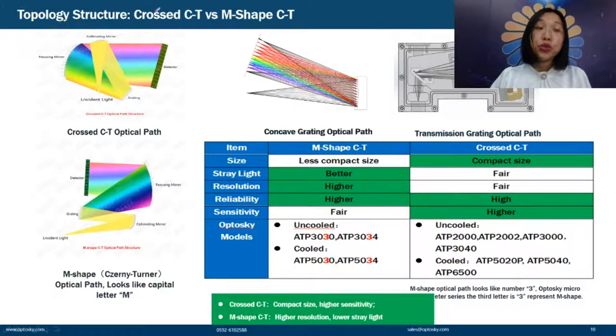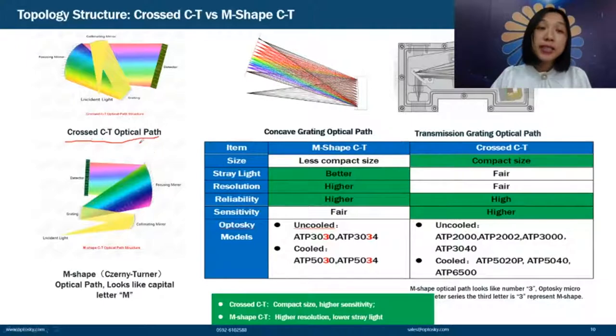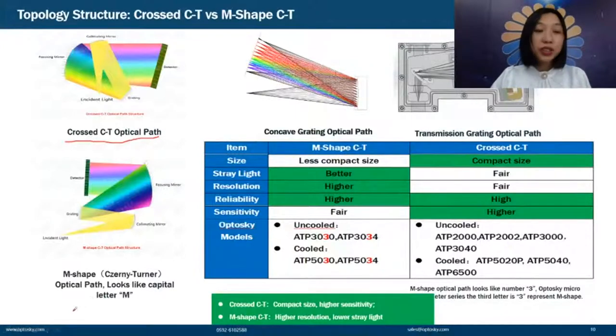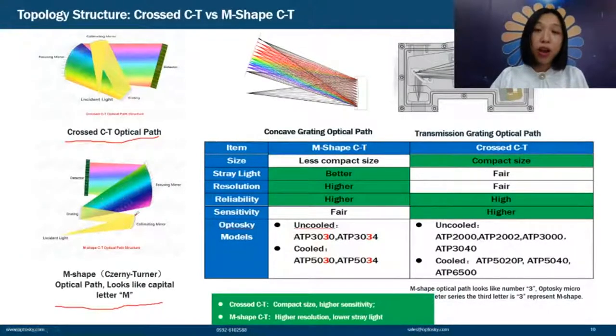The cross-CT optical path is used most commonly in spectrometers because it has a compact size and very good sensitivity. The M-shaped CT optical path looks like a capital letter M — it is an unfolded optical path. M-shaped CT has a slightly larger size, but better resolution, lower stray light, and better reliability.